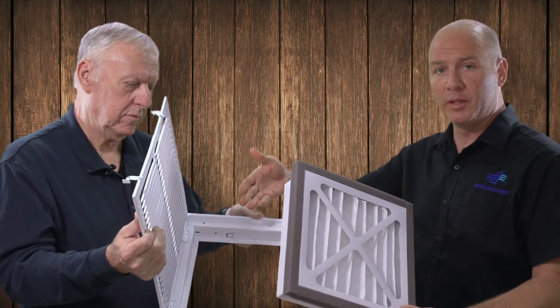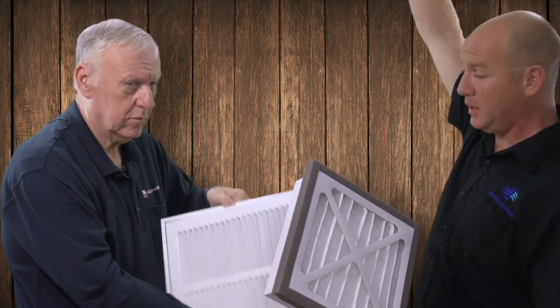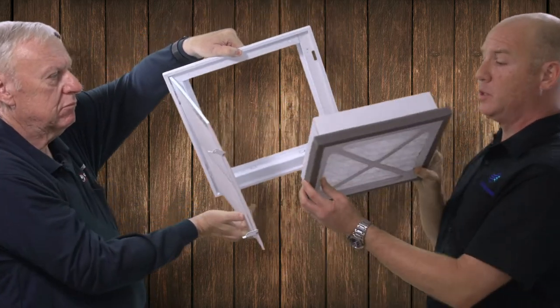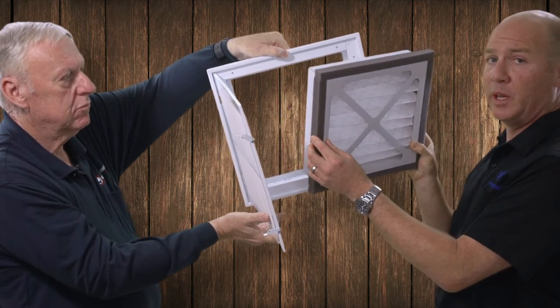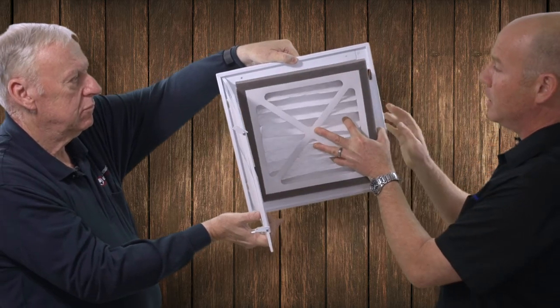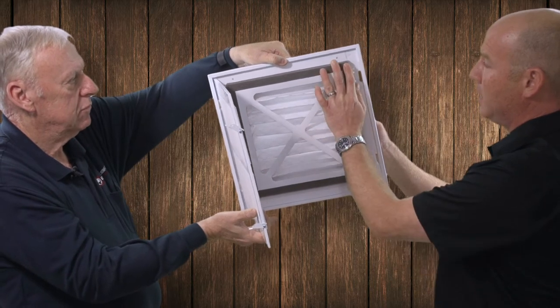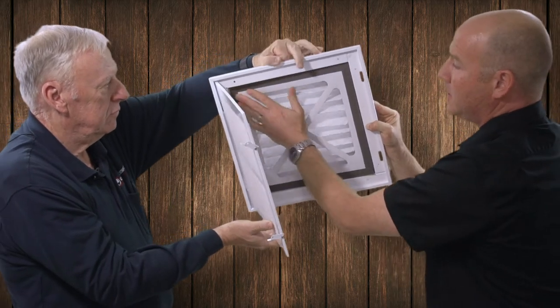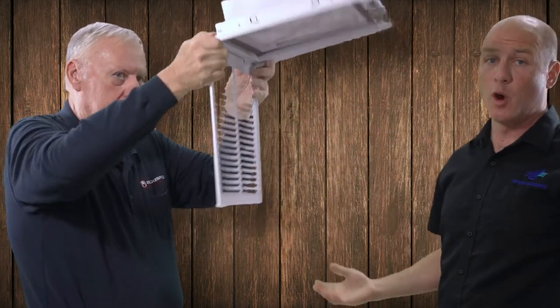This is a filter grill that's found in most homes. It's installed in the ceiling, and this door swings down. How this filter is installed: you place this foam header — which creates a really great seal to keep air from bypassing around it. All you do is take out the one-inch filter that was in there, slide this end in first, then push it in, and that creates the seal you need. As you can see, there is almost zero air going around this filter — no bypass.